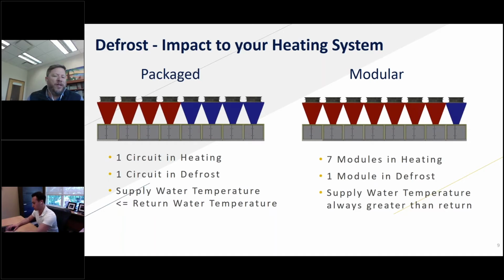So when you operate like that while in defrost, you're going to, in a lot of cases, actually end up with a supply water temperature that could be below the return water temperature. So we have a system or a loop that we're trying to heat, but when we go into defrost, if we're just running that one machine, we're actually doing the opposite. We're actually cooling that down, okay?